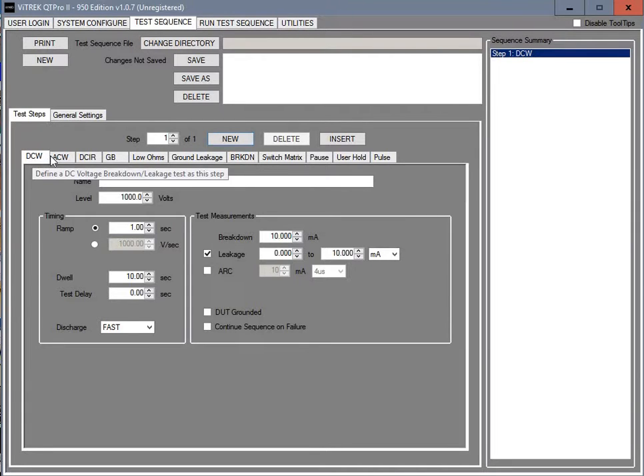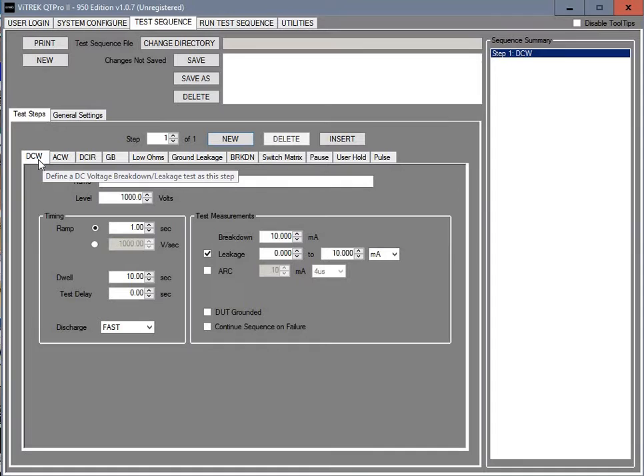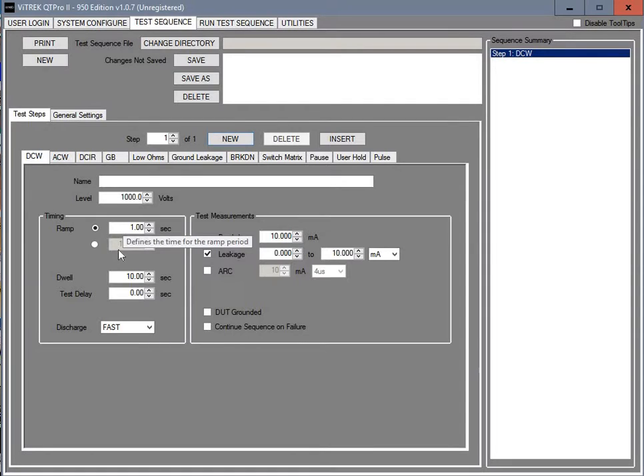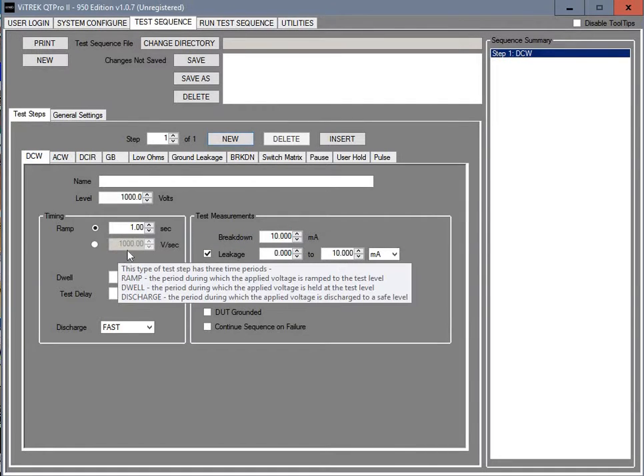In this case the default is DCW, which is a DC withstand high pot test. It's set for a thousand volts as your default. A one second ramp. You can also choose to do it in volts per second if that's what you would like.